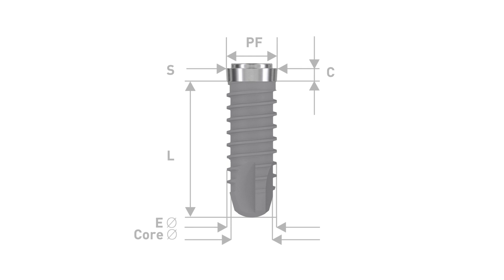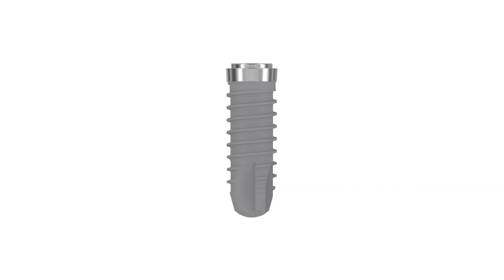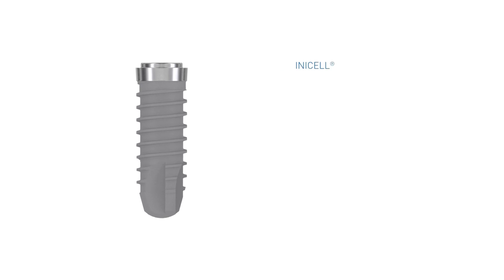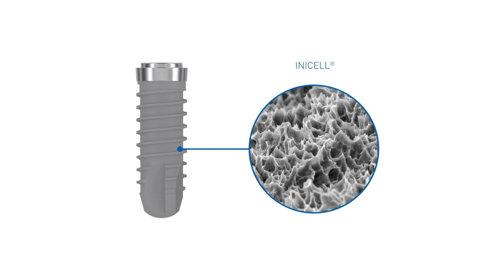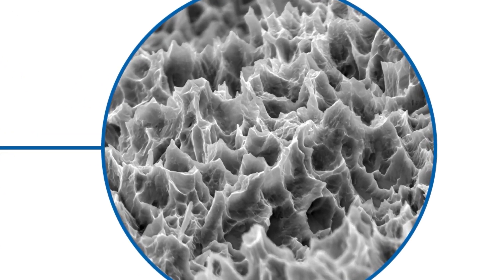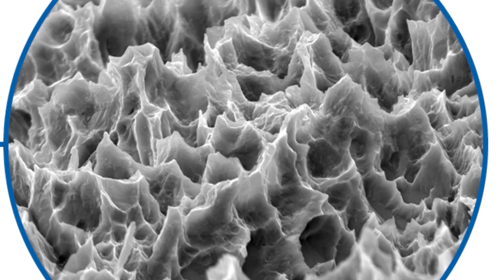Other specifications include the shoulder, which refers to the coronal level of the implant, the endosseous length, the endosseous diameter, and the core diameter, which correlates to the diameter of the drill hole. All Thommen Medical implants are available with the superhydrophilic NSL surface, which is the conditioned state of the standard sandblasted and thermal acid etched surface.